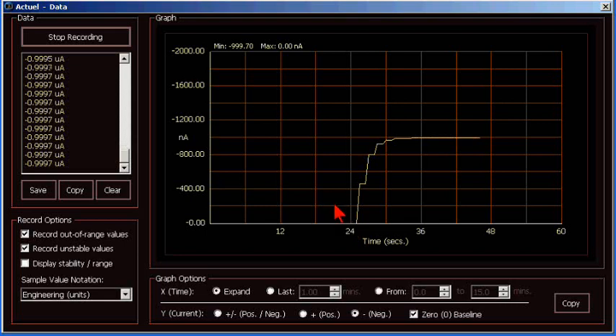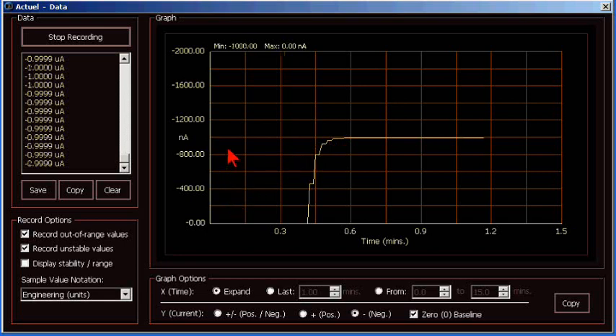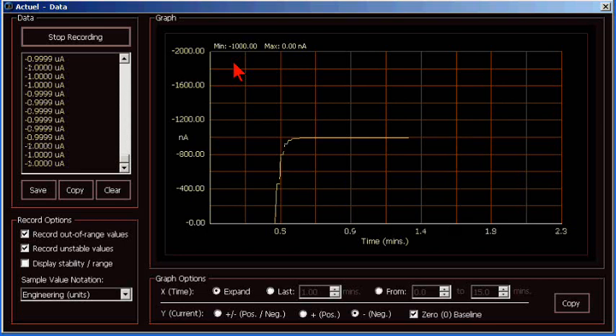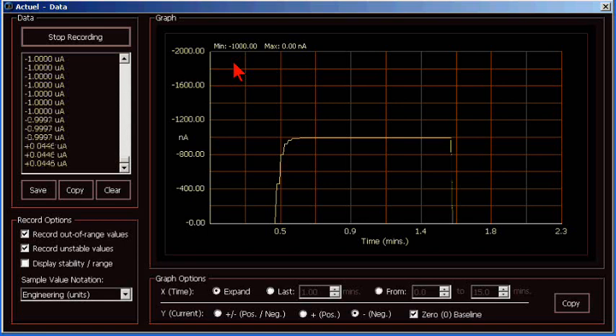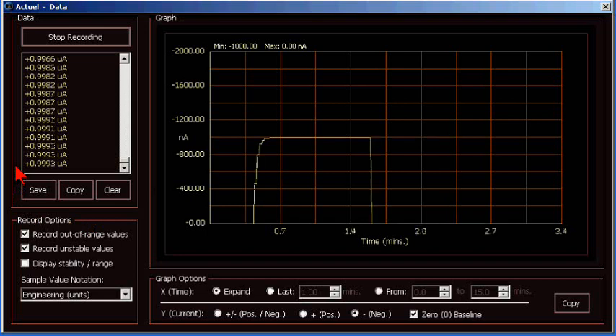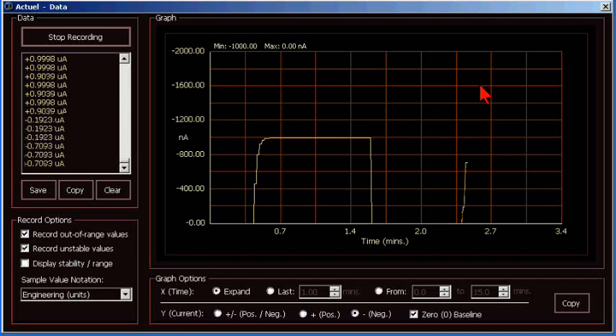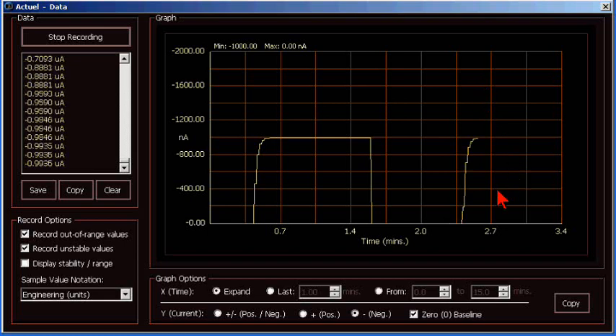And again, if we reverse polarity, the graph will not go below zero. So this graph type is useful for measuring electron currents on a vacuum system or any negative current source. Again, increase the current back up. The graph goes positive.